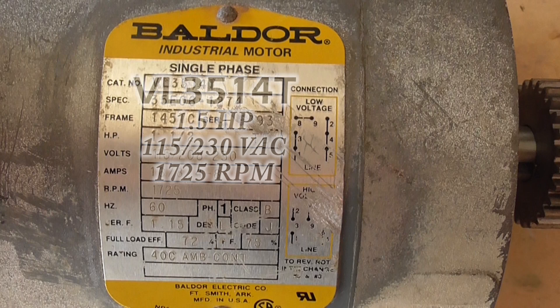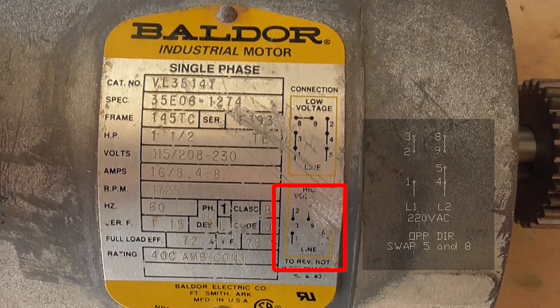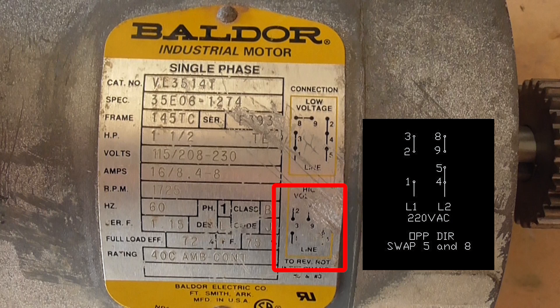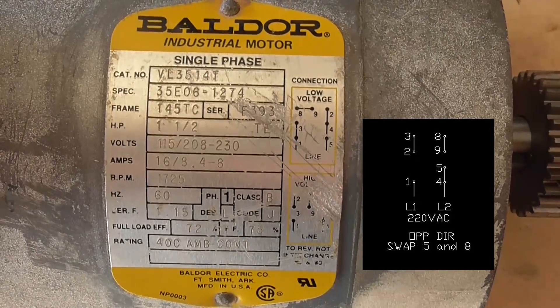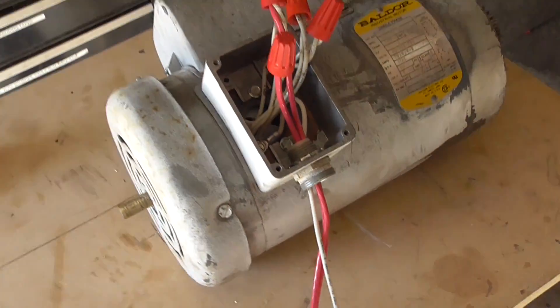This is a Baldor VL3514T motor. It's one and a half horsepower and it can be wired for 115 or 230 volts AC. Unfortunately, the connection diagram for the 230 volts is scratched out, so here's my drawing of those connections. I'm not sure this motor will actually run, so I'm going to try it out and I made the connections as shown on the diagram.